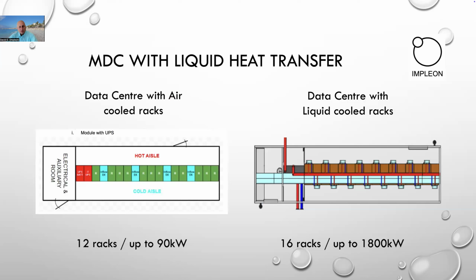Also, I want to talk about densifying and having less carbon on the building level. Here you can see two modular open source data centers. On the left, air cooled, and here the limit is indoor coolers. We have three working, one reserve. Each indoor cooler can provide 30 kilowatts, so overall 90 kilowatts. This is the limit. If we go to the AI dedicated racks, we have door heat exchangers and on-chip cooling, so we can achieve 100 to 120 kilowatts per rack, and 16 of them can form 1.8 megawatts. So this is how we can reduce the surface area up to 20 times.